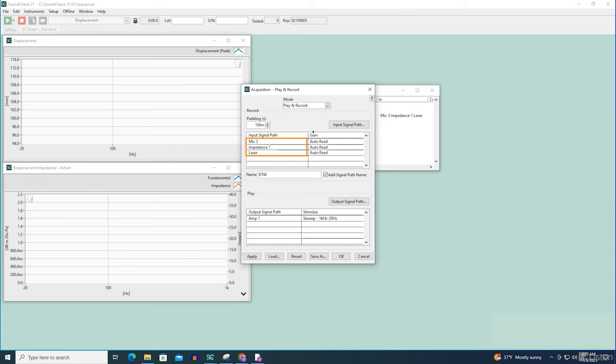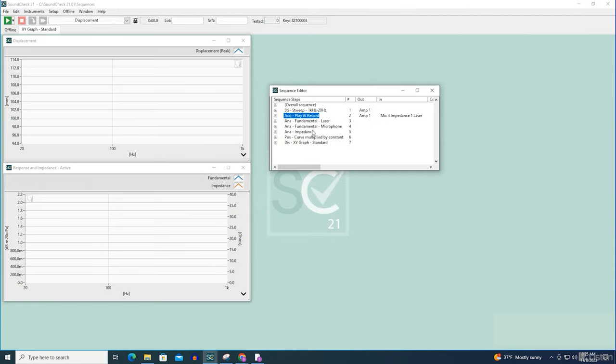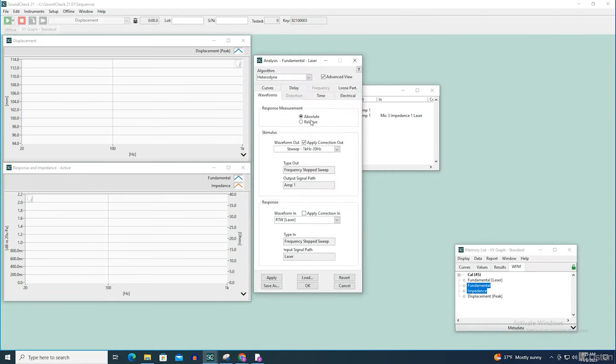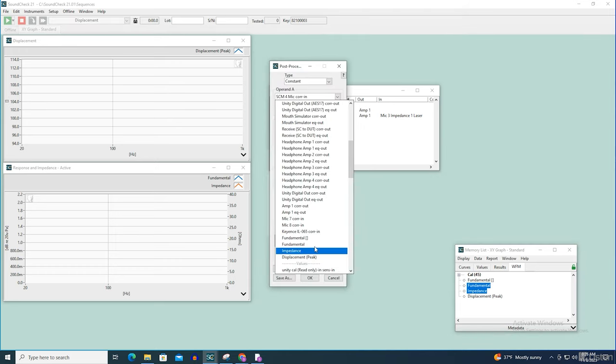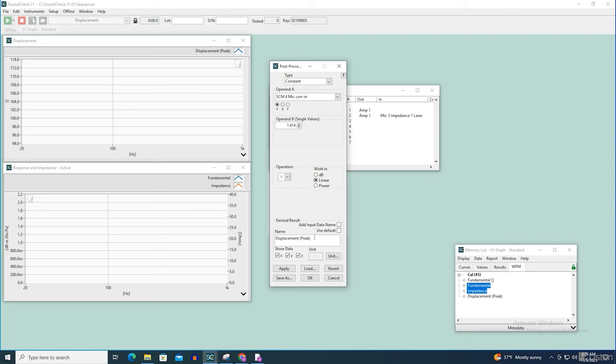The recorded time waveform from the laser can be analyzed just like any other waveform, but there's one additional post-processing step required after analysis: converting the displacement level from RMS to peak.